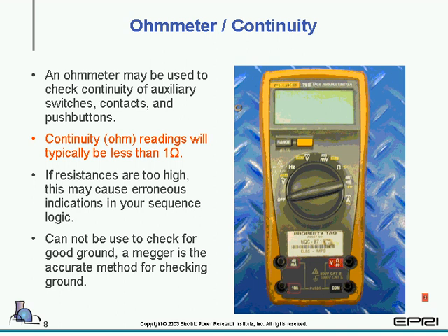Ohm meter and continuity. These are not necessarily the same tests, even though they're talked about on the same slide. An ohm meter gives an ohmic value, such as if you were looking at a pickup coil or a trip coil, something along those lines. You're looking for a band of acceptance. Continuity is a go, no-go gauge test, if you will. As a rule of thumb, less than 1 ohm would be considered continuity. You might want to remember that if you're taking the test.